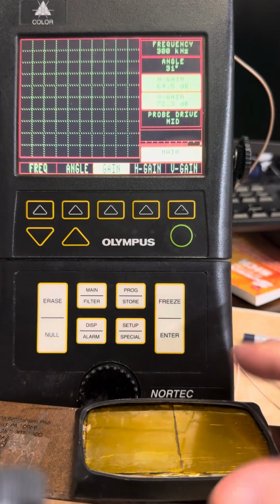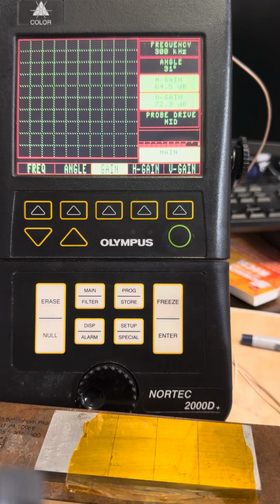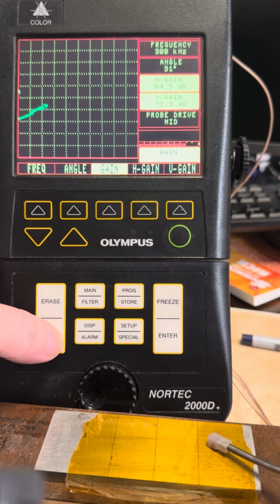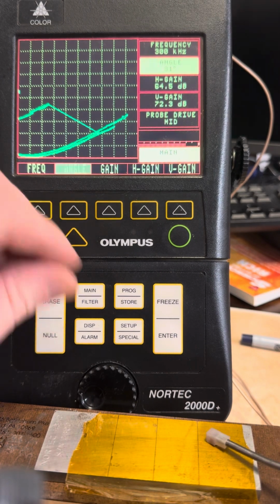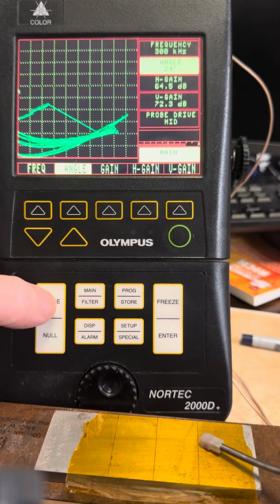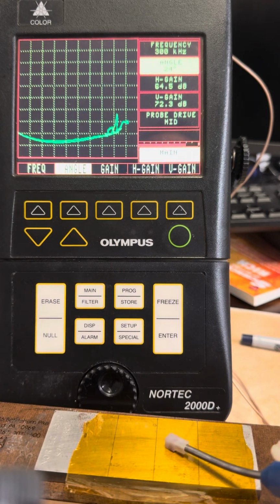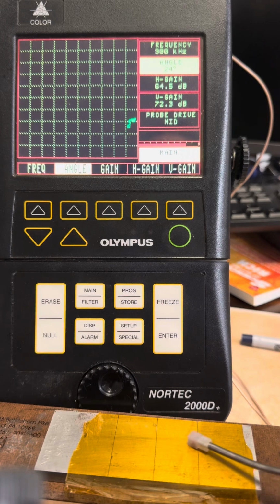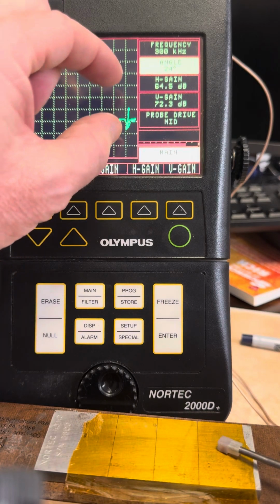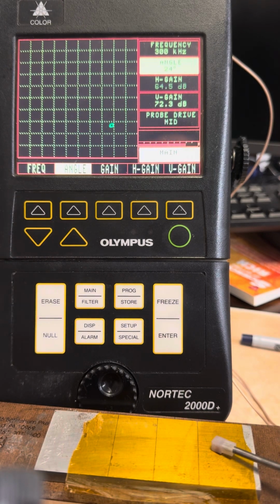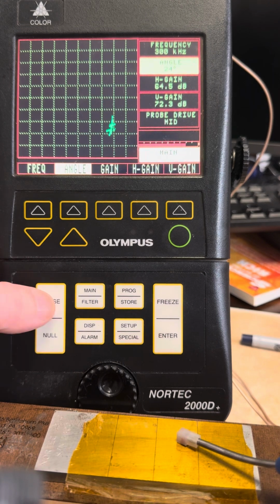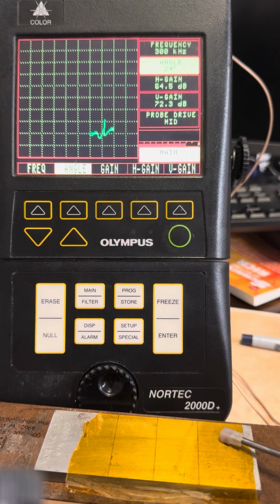So let me go, just to show you, I'll go here and I'll null on the cal block. And if I set that noise horizontal, this is your smallest indication right here. That's about 2 divisions. So I'll erase it and I'll go over that again. So by setting your cal block simulated crack to full screen height, the 0.008 inch deep crack in the cal block is about 1 division.